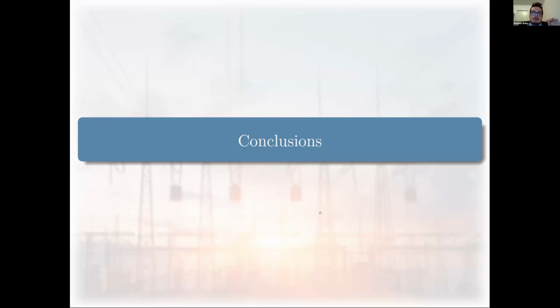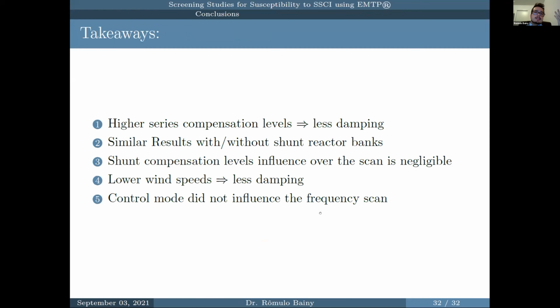I want to share some conclusions that we got with these studies that we performed using EMTP. First, higher series compensation levels are going to result in less damping, more negative damping.